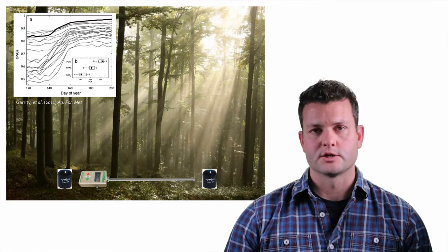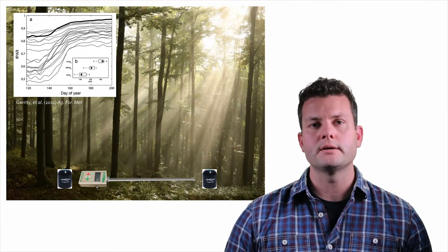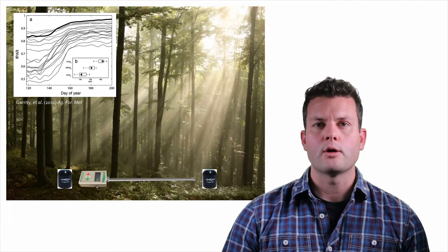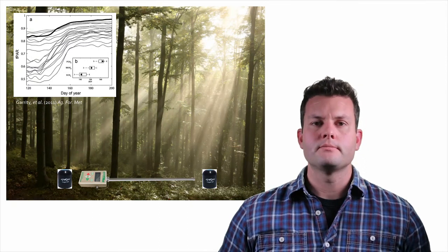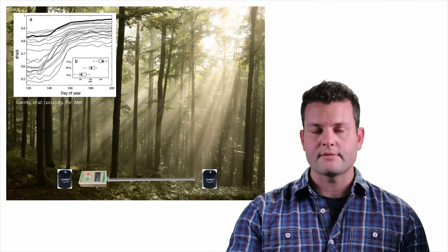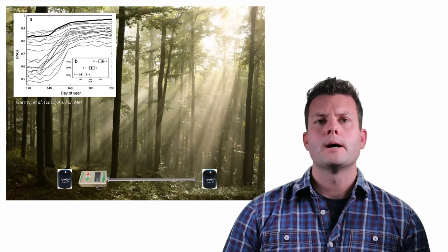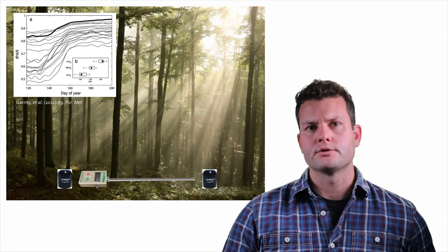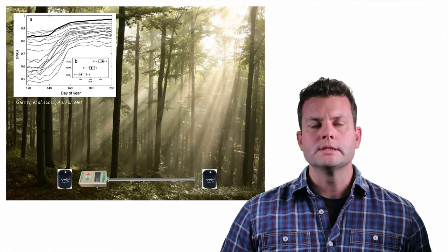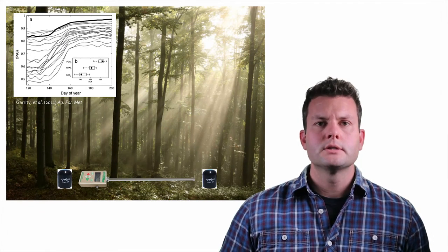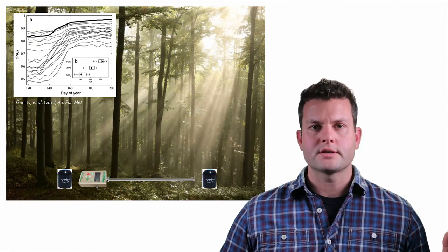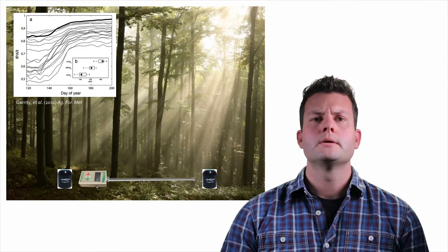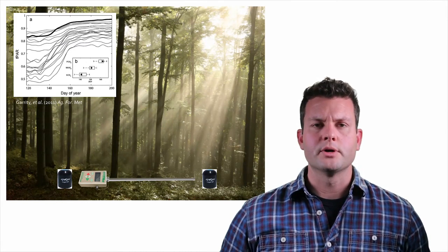And so the LP80 has this wand that comes out of the handheld unit, and that wand is about 80 centimeters long, and there are 80 independent PAR sensors in that wand. The readings that you get from the wand are actually a spatial average across the readings of all of those sensors in the wand. And this was shown by some researchers several years ago: in canopies where clumping is present, if you take an average across a linear transect, you tend to reduce the amount of error associated with the clumping. So that's already physically built into the LP80.